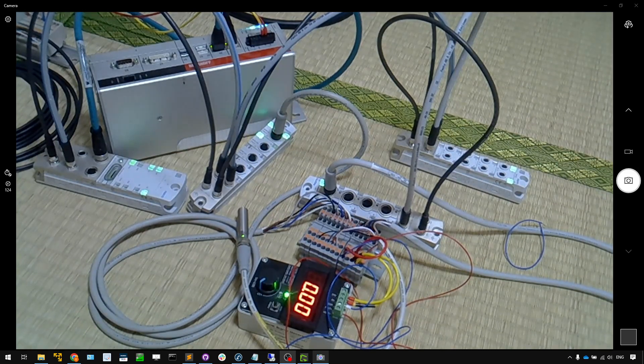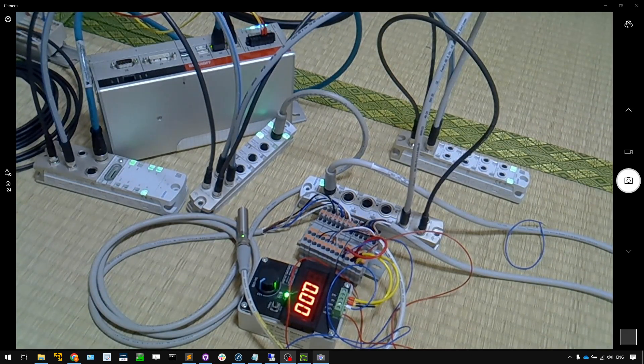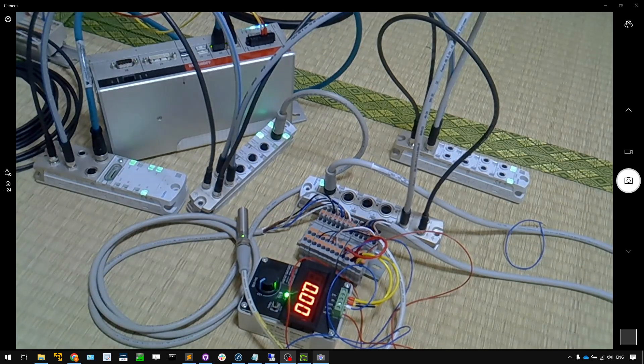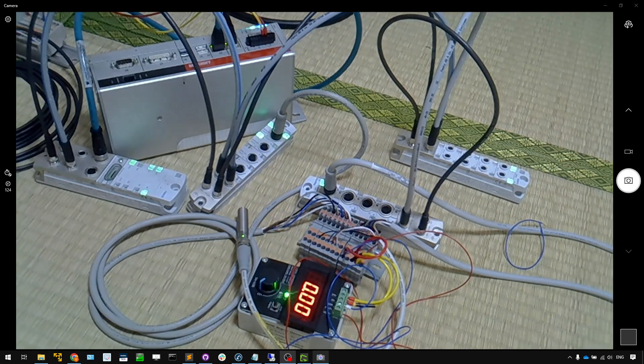They don't have a long cable directly connected inside. You can see there is a black cable and a grey cable here. The black cable is 24V DC supply — you need a 24V DC supply connected to each module. The grey cable is the communication cable, which handles communication between these three modules and the interface module, sending data or commands to set output ports on or off, or to configure the IO-Link.